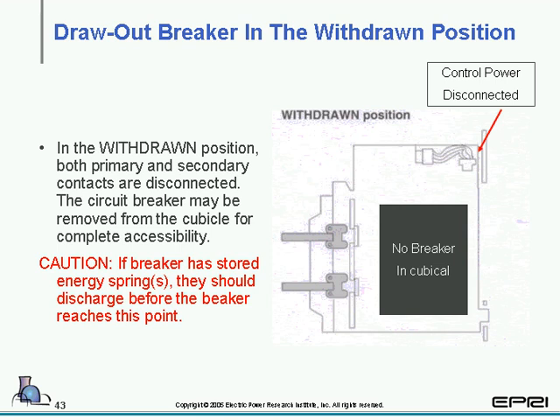And the last one we have is the withdrawn position. Now, the withdrawn position differs from the disconnect position in that the breaker is not being held in the cubicle. A term that is normally used is seismically, which most of you nuclear people may understand if you're from fossil fuel. It means that the breaker, in the case of an earthquake, will not come out of the cubicle. Excuse me. If it's physically held in the cubicle, it's in the disconnect position. If the breaker can be removed and inserted, it's in the withdrawn position.